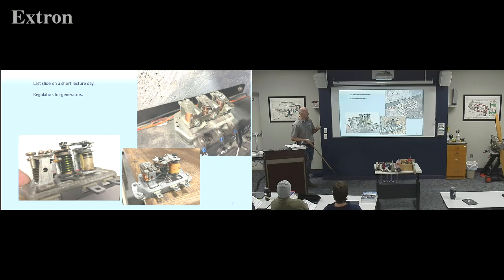Now if we get into a situation where our generator stops making voltage - typically it's not going to be these guys opening, because they're just opening when you max out our voltage, right? But if we get into a situation where it's trying to motorize this again, when the power can come backwards through there, and it actually has to come backwards for a slight amount of time, once the power is going backwards through that coil again, this guy's going to go, the big heavy guy is going to go, oh, Wimpy, I'm not on your team anymore. And he's a lot stronger, and he'll overpower Wimpy Man, and he'll open the contacts basically back up, as he goes, I'm going the other way.